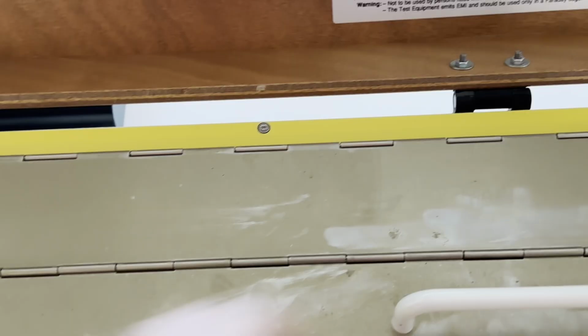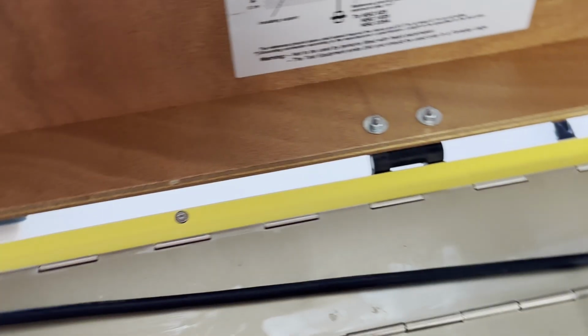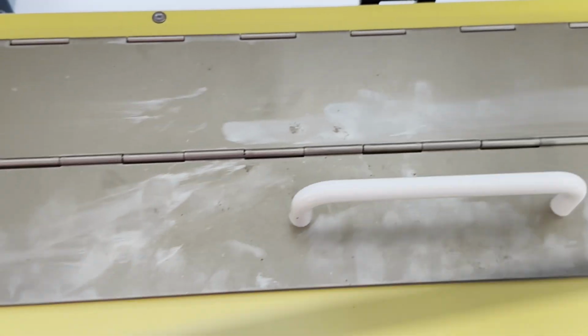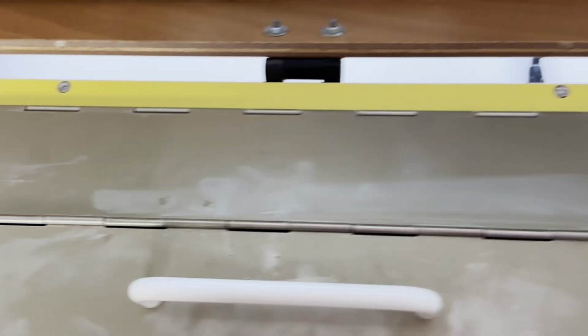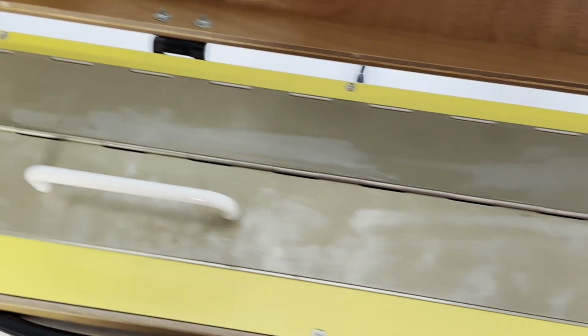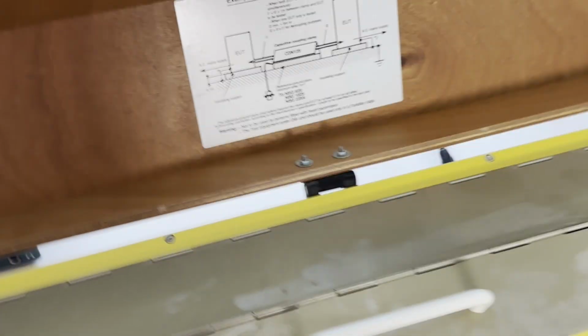And it's important to know that I've seen people put cables like this, and obviously that's not going to work very well. So it's quite important that you open it and put the cable in the middle so that the discharge or the transient can be applied to it. And in this case, I'm going to use an HDMI cable, which I'm going to connect to my laptop on one side and to the display on the other.